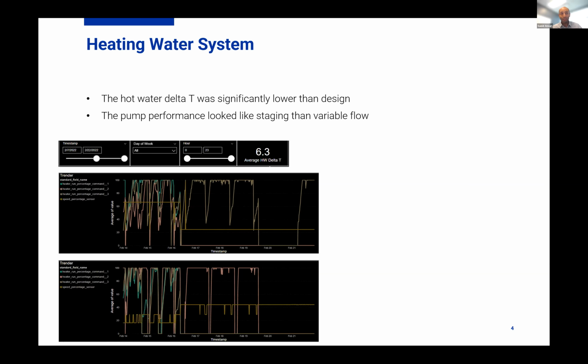One of the first things DB Technologies found for us was when they looked at the hot water system, they quickly realized our performance was way off. The building was designed to have a delta T of 18 degrees, and we were operating around 6 degrees. What's going on here? This was interesting because I knew things were going to get missed. I was also a commissioning agent when I started my career, and I knew you can't commission a complex heating water system in 2-3 hours and say everything's working out, but I wasn't expecting this.